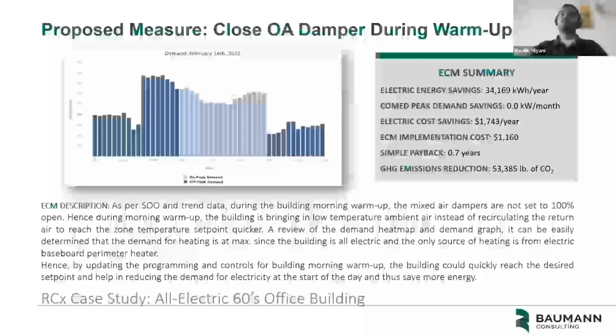And the next ECM that we identified was the sequence of operation. As I already mentioned earlier, over a period of time there are high chances the sequence of operation might change since it was not recommissioned properly. Looking into the trend data and the utility bill, we came to know that while the building warm-up was happening during the investigation phase, the OA damper was not completely closed. It was continuously bringing in outside air, due to which it was taking a lot of time for the building to reach the desired set point during the early morning time.